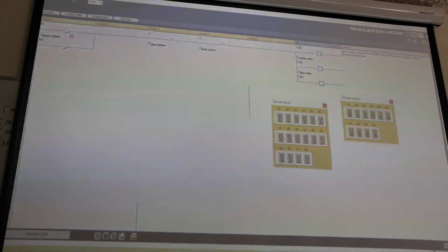Okay, so when I hit this button here, it powers us up, which puts us around and bypasses the switch. That's my latch. So we'll do that again. I start the switch, I stop the switch, and it's latched on. It's going to run on forever until that float switch comes off, and then the float switch pops it off. Okay, so that's using a memory. I don't have to use a memory. Hey, that's good code, that works fine.